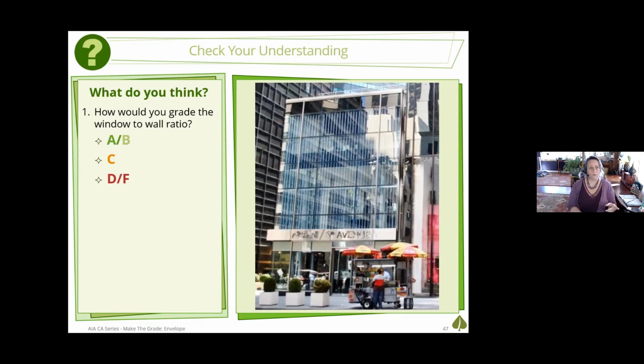Karen's asking, well, what if it's dynamic glazing? If it's dynamic glazing, I get to take the value of the lowest solar heat gain coefficient in my calculations, but only if it's automatic dynamic glazing, meaning there's a control so that when the sun hits this facade, it darkens the glass. Usually there's an electric current that goes into the gas between the two pieces of glass that darkens it, and I get to use that lower solar heat gain coefficient when I have dynamic glazing, which is great.